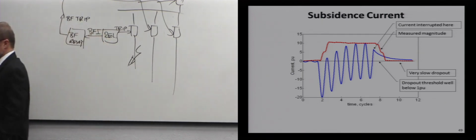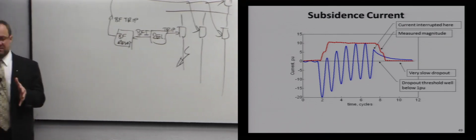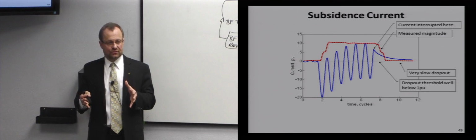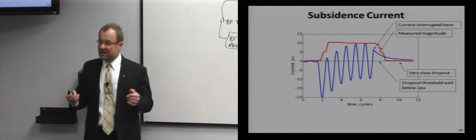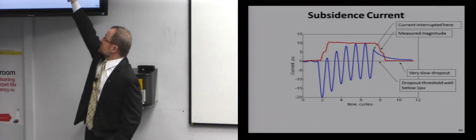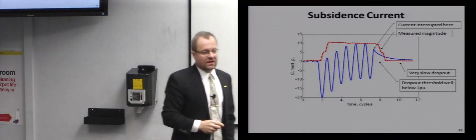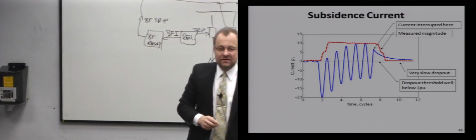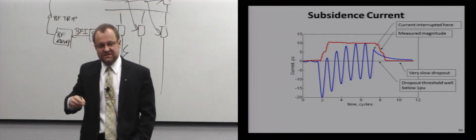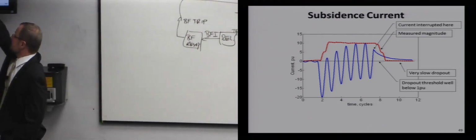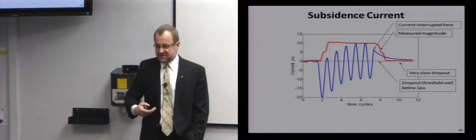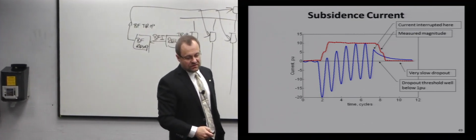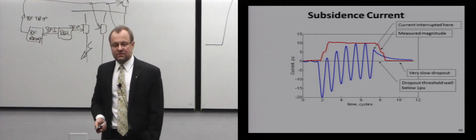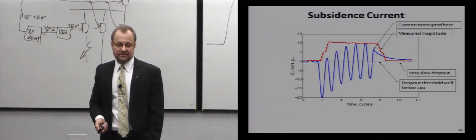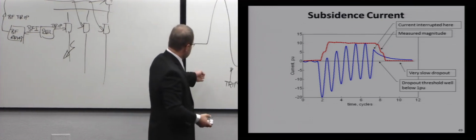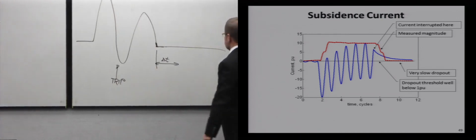Now, the Fourier filter that we are using for a phasor estimation, what is the frequency it's tuned to? 60 hertz, right? In that subsidence current, that exponential decay that happens because of CT saturation, do you have 60 hertz? Yeah, you do. And we are looking for 60 hertz. So that subsidence current will delay, if I zoomed on that red curve, it will be there for a while because there is legitimate 60 hertz component, right? So in this case, it may take me more than a cycle or two to realize that the current is gone. Can I live with this? Yeah, I may just set my timer to here, and that's fine.